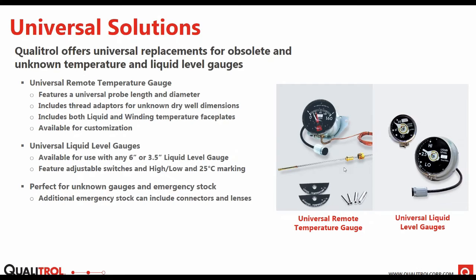As far as our universal liquid level gauges go, we have them for both the 6-inch and the 3.5-inch style liquid level gauges. They feature adjustable switches and adjustable high and low indication points with these little flag indicators here. And these will work with any liquid level gauge flange that was a Qualitrol. So the back end, the flange portion, which comes back to testing the liquid level gauges, the case is usually the part that needs to be replaced, and the flange is typically okay.